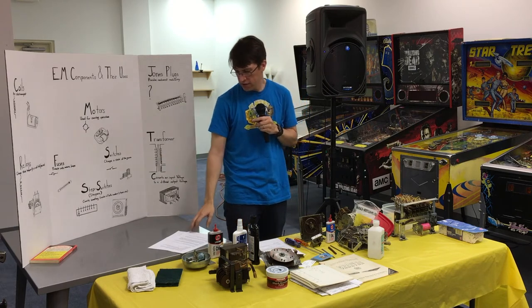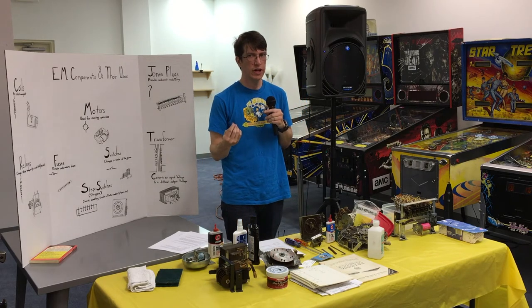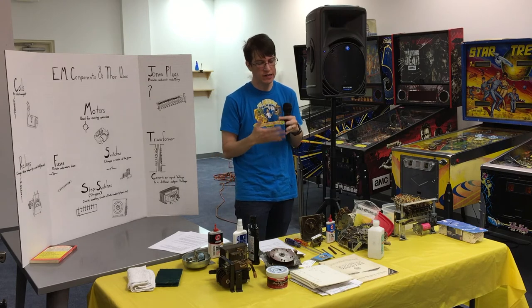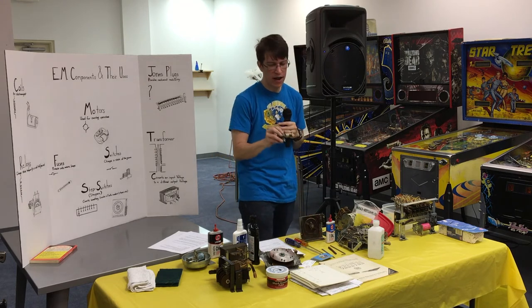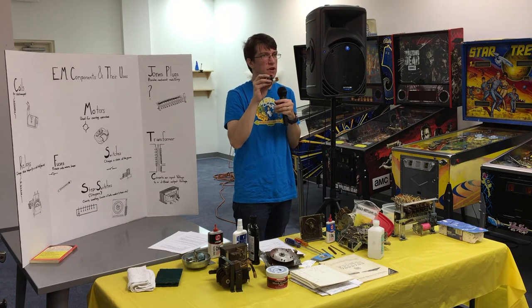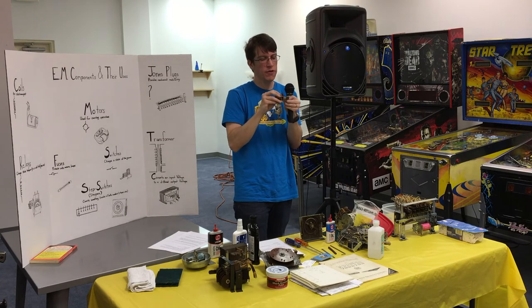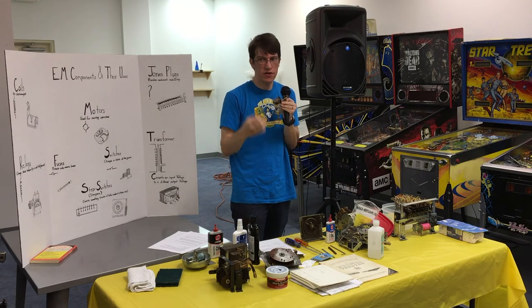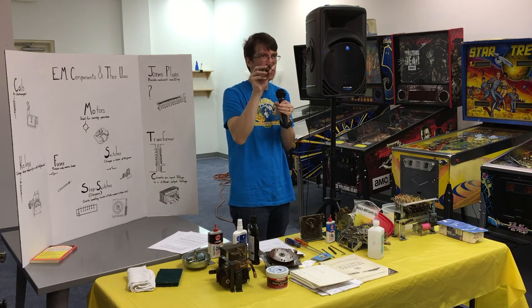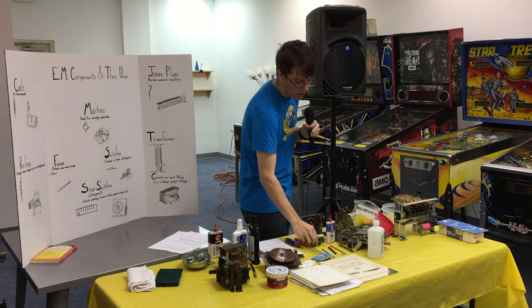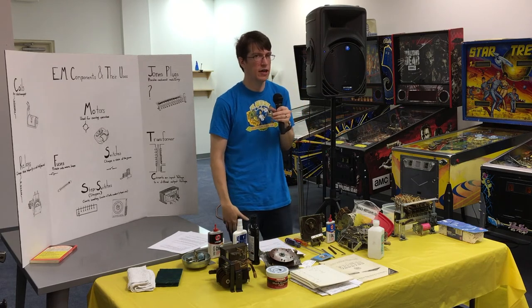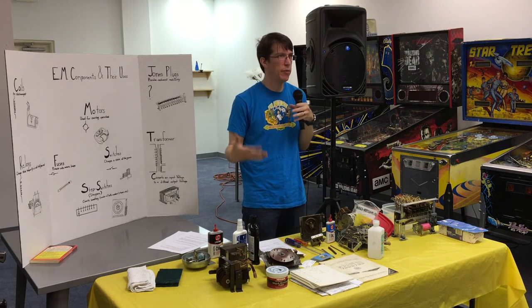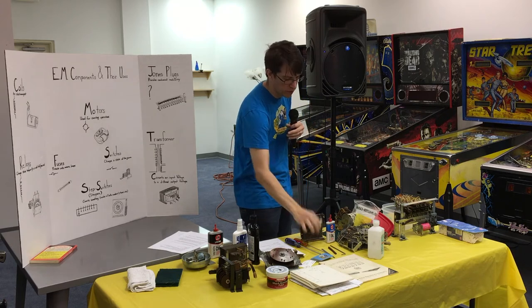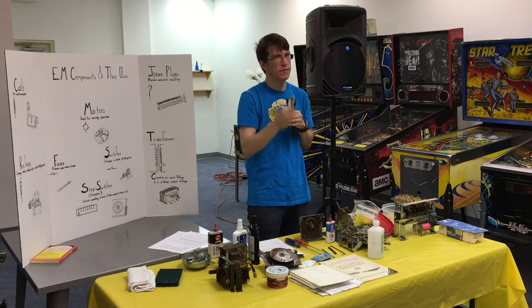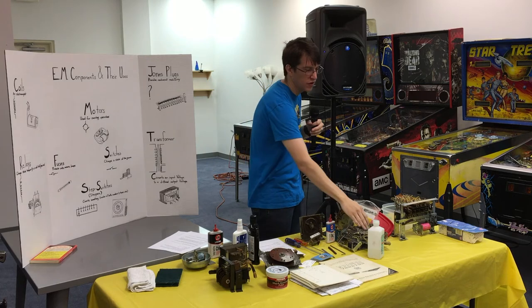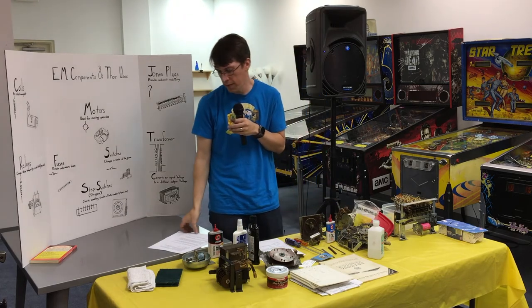So just check the state of those. They also, if they're dirty, will arc. An easy thing to check and see if you're having odd problems: are your switches arcing? If you turn the lights off, look at it, you see a bunch of green sparks. That's a clue that you've got some dirt somewhere. Some things will always arc just because of their nature, they're very high power. But generally speaking, in a relay, you don't want those sparks. Switches on a score motor, you don't want the sparks, if you can avoid them.